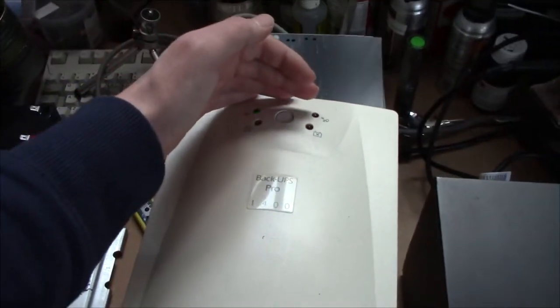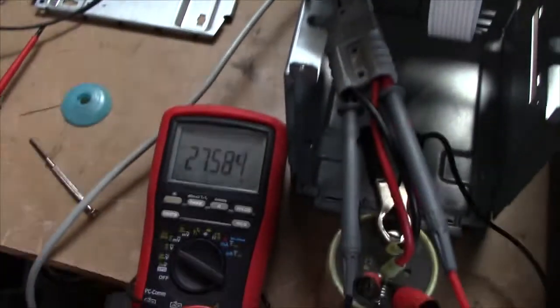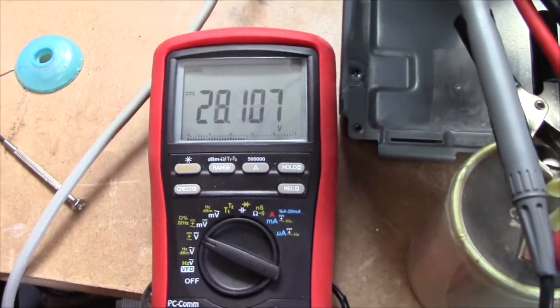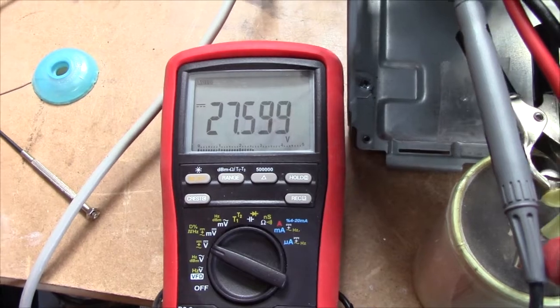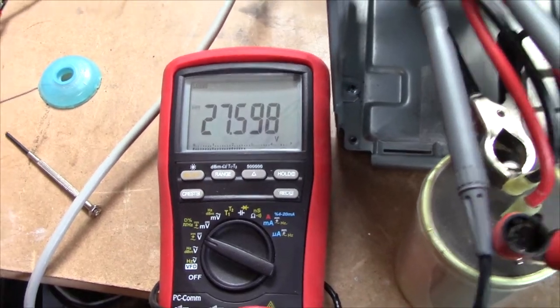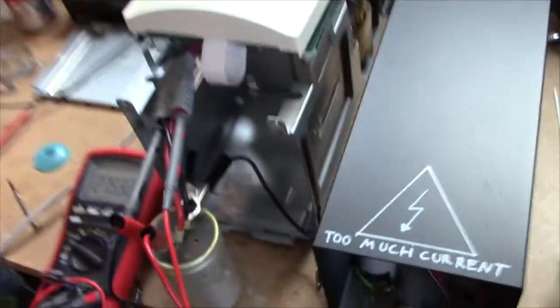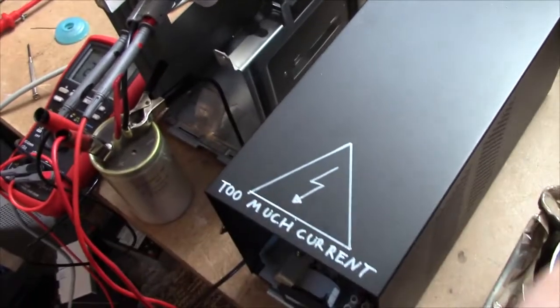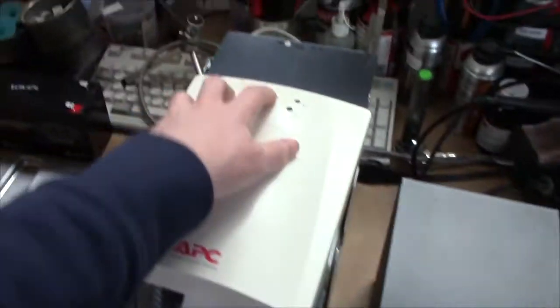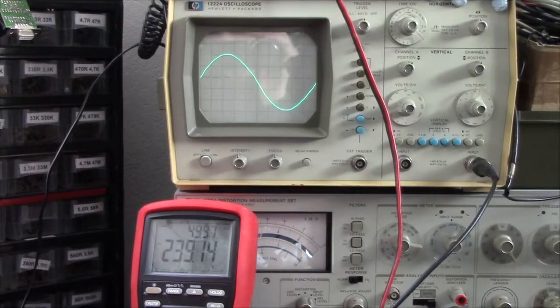I've got my normal 500 watt load hooked up. This thing is going to run a self test. So let's see what happens to the voltage. It wasn't happy. This thing has too high an output impedance. Oh shut up.